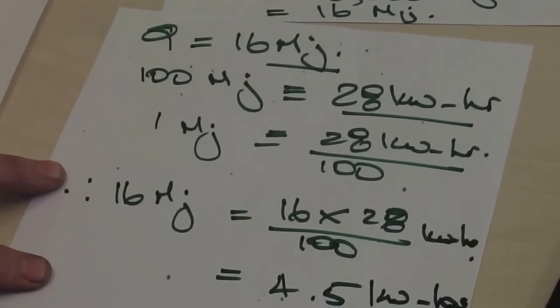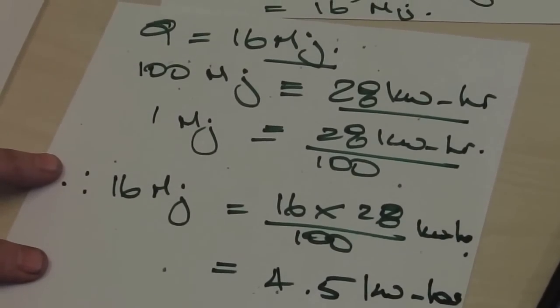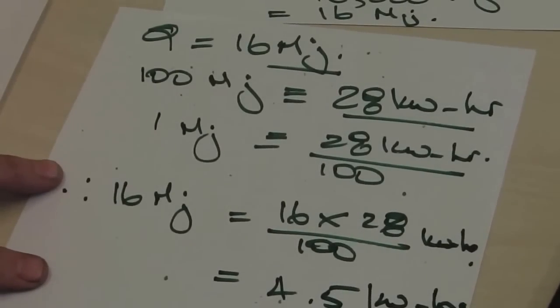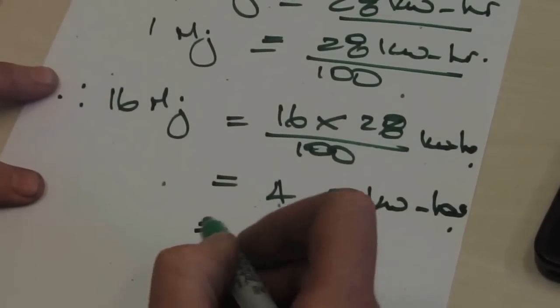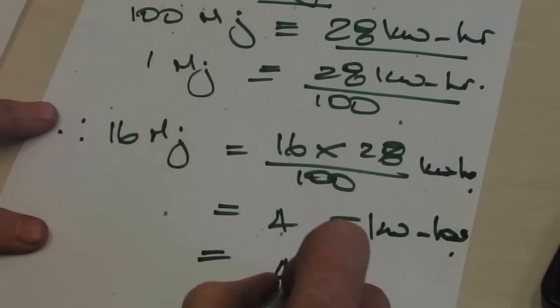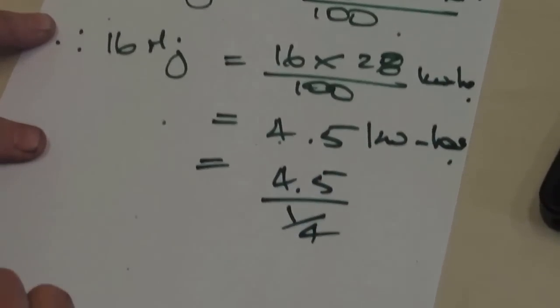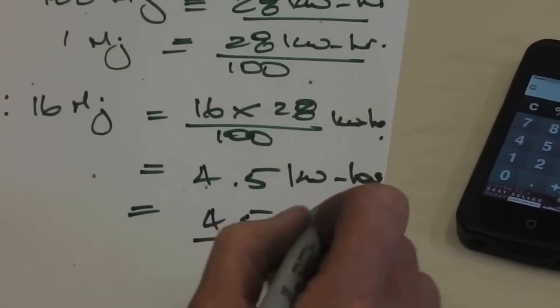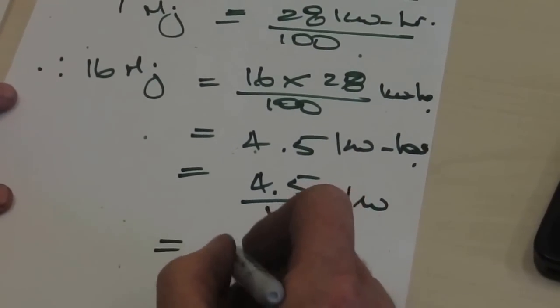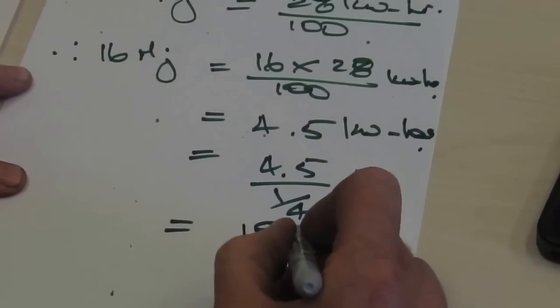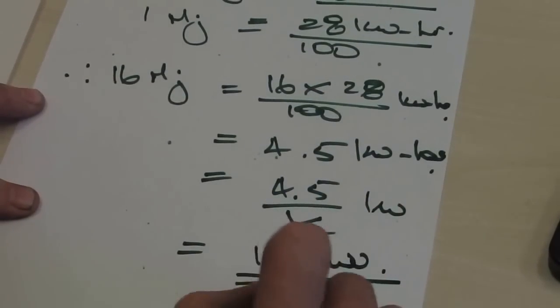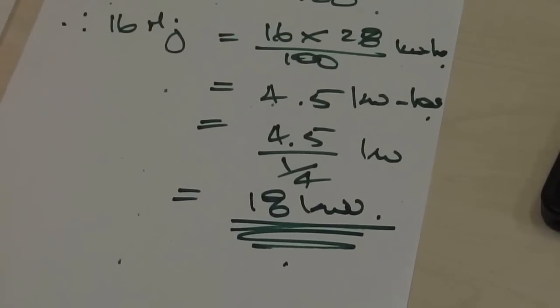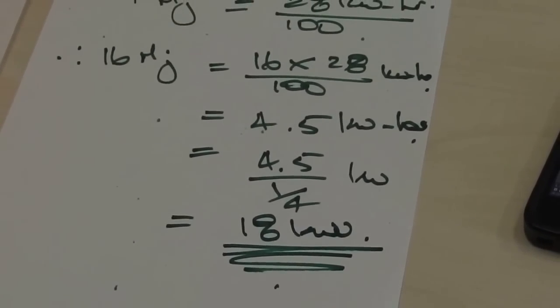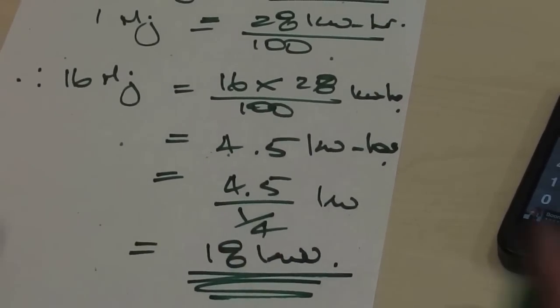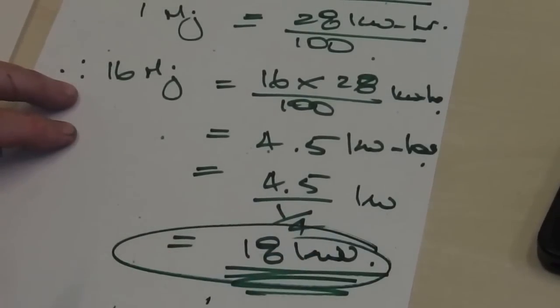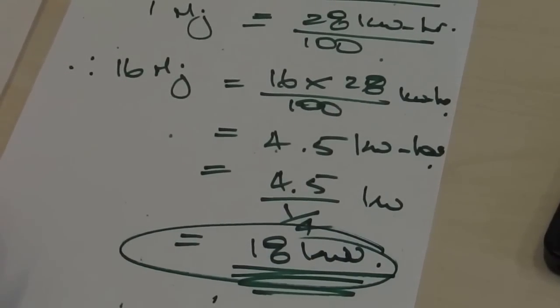Now we only ran for about 15 minutes, which is a quarter of an hour. So the amount of energy we needed to do what we did was 4.5 on a quarter of an hour kilowatts. So that is equal to around about 18 kilowatts required to lift 200 litres of water by 20 degrees C. Therefore, our heat exchanger over the average period there was exchanging about 18 kilowatts of heat over that 15 odd minutes.